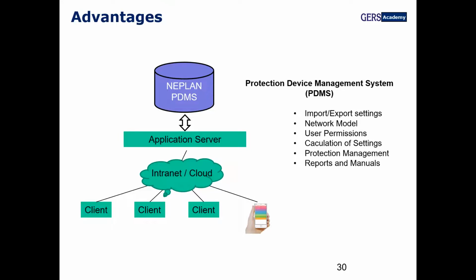So if we are able to integrate the protection device management system, you can check in real time the settings, and you can assess if that setting is proper or not. Why? Because if you get the existing setting and run the short circuit simulation, you can verify if the setting is proper or not.